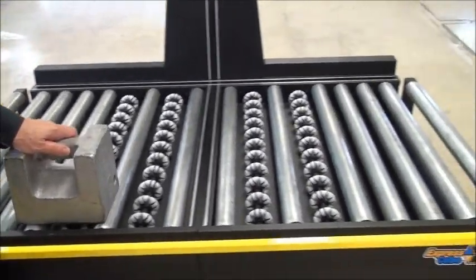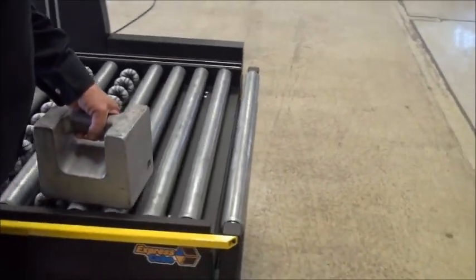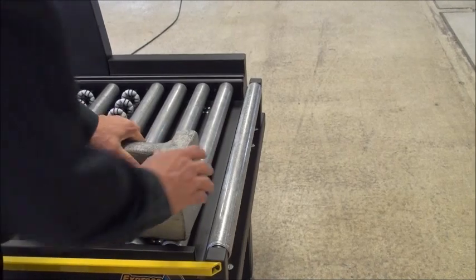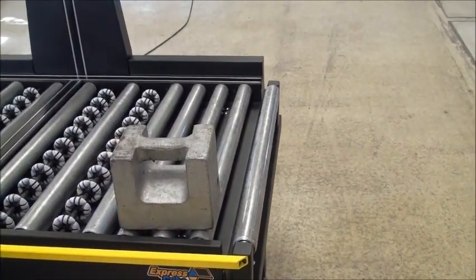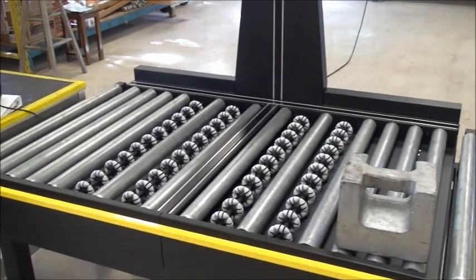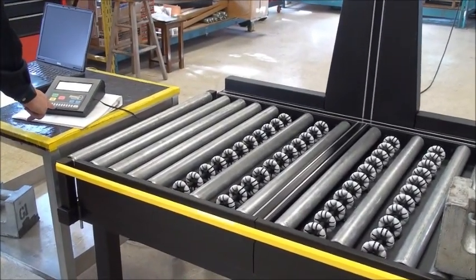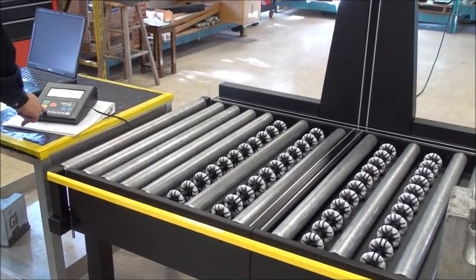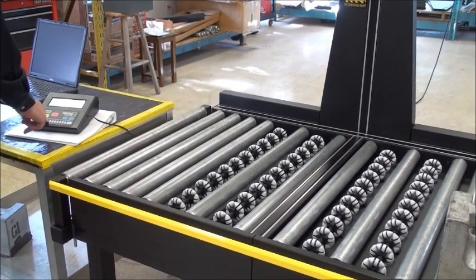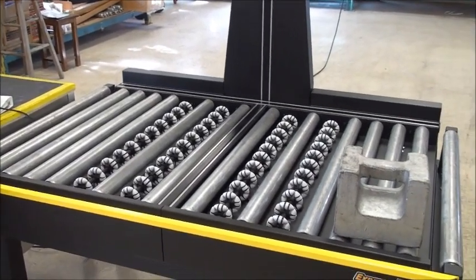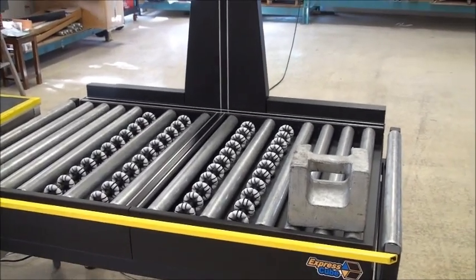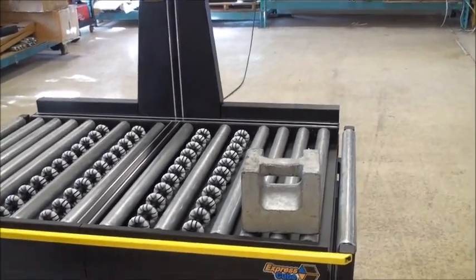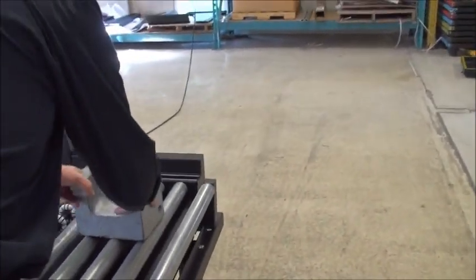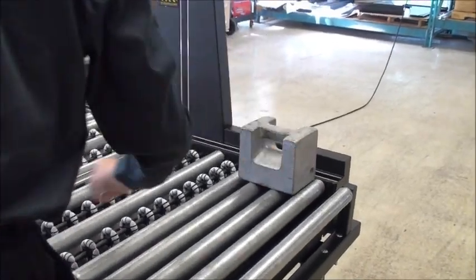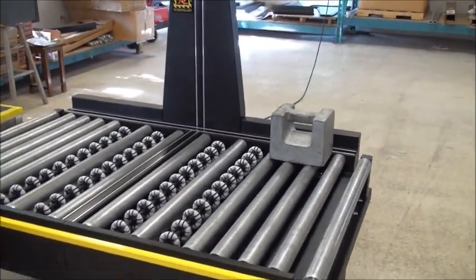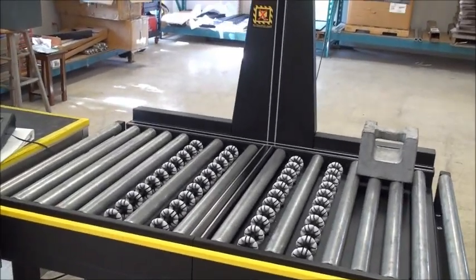I move this over to another part of the table here. Okay, that'll be my third load cell. As I say, it doesn't matter the order, but they should be all over top of each of the load cells, or close to the load cells. In this case I'm going to hit record number 3. I'm recording. Okay, it says recorded here. The lights have stopped flashing. The last one I have here, I move it over to this part of the table. And I now record for load cell number 4.